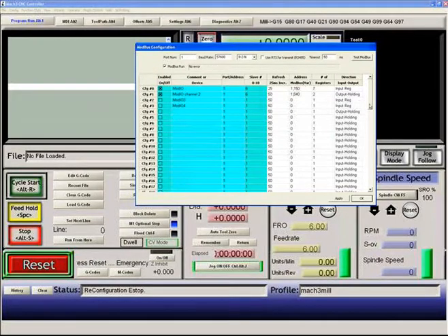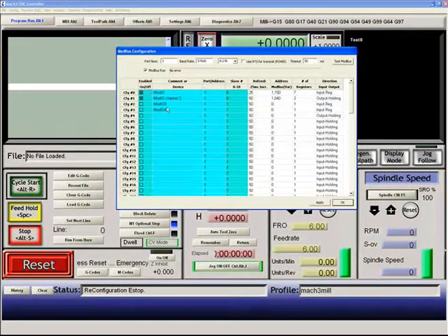And here on the far left-hand side, we have configuration numbers, and you can have up to 63 of these configurations. Each configuration can hold up to 127 transfer registers. So let's take a look at a quick example. As you can see, if you can read this, and you probably can't, so I'll read it off to you. I have configuration 0 enabled. I've given it a name of Mod I/O.